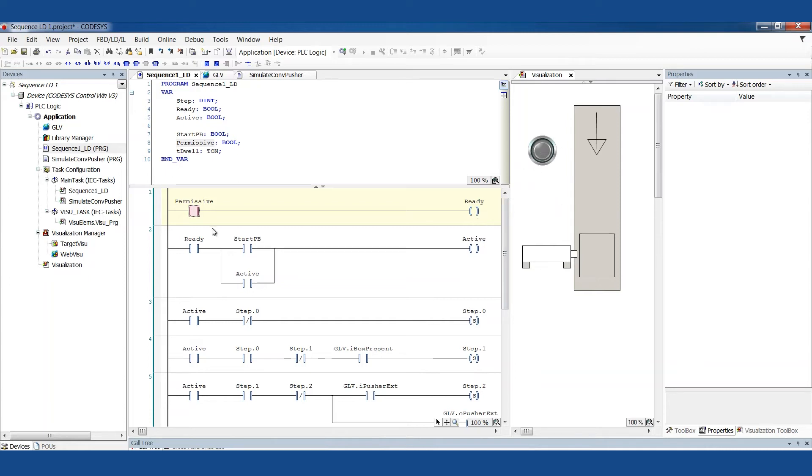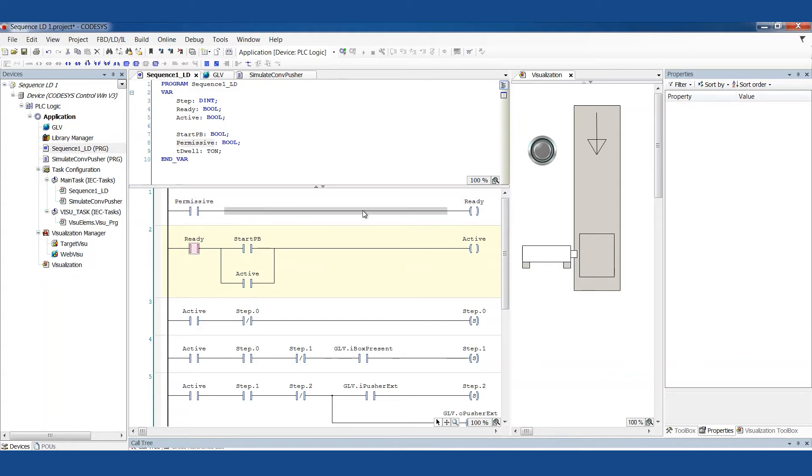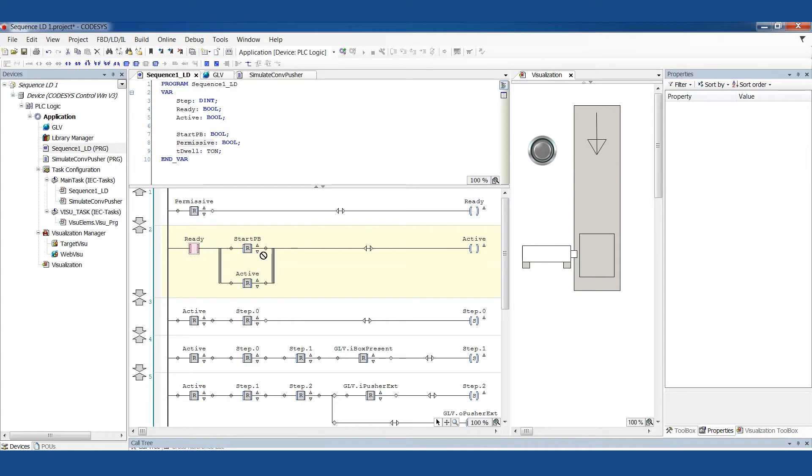The next rung here is showing that this sequence is active. I've seen some people have a done bit instead of an active bit. I've also seen this be latched and unlatched, or in CODESYS terms, set and reset, instead of latching itself in here like I've done. So this is saying, if it's ready, and again that's the summation of all these permissive things that could be here, if it's ready and whatever start condition is met, that's my start push button, then you're active and latch yourself in. You may notice that this is maybe slightly backwards from our normal start condition, latch, and stop conditions. I'm doing this just because it makes more sense in my mind: check to make sure it's ready and then consider starting.